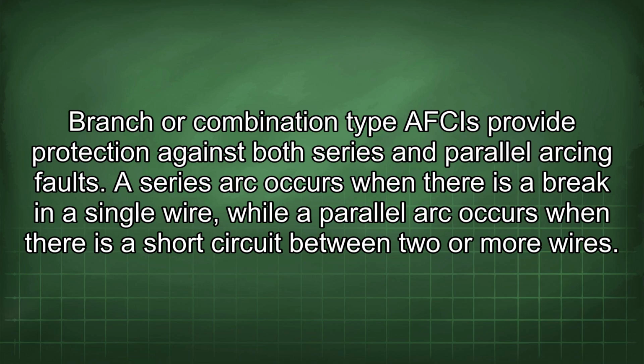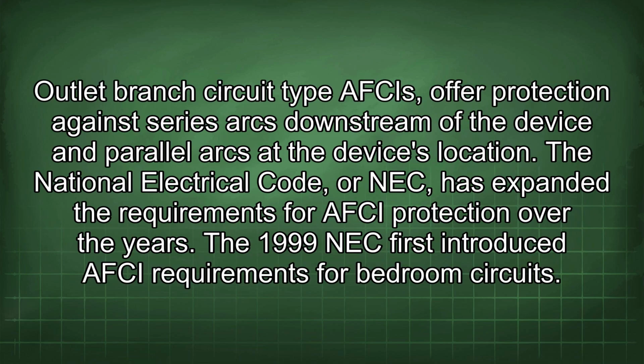Branch or combination type AFCIs provide protection against both series and parallel arcing faults. A series arc occurs when there is a break in a single wire, while a parallel arc occurs when there is a short circuit between 2 or more wires. Outlet branch circuit type AFCIs offer protection against series arcs downstream of the device and parallel arcs at the device's location. The National Electrical Code, or NEC, has expanded the requirements for AFCI protection over the years.